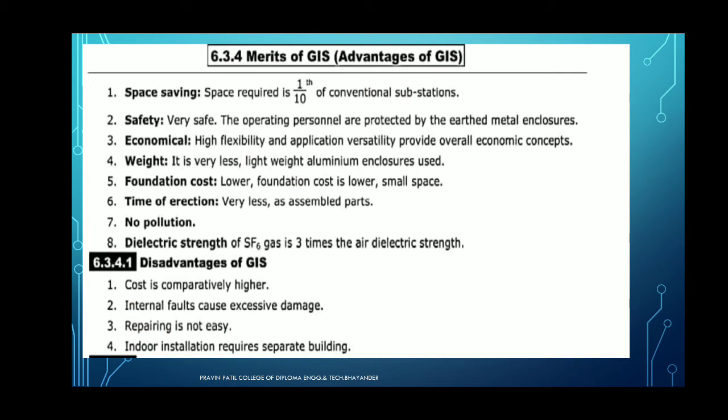Economically it has high flexibility, is applicable and versatile, and provides an overall economic concept. Its weight is very less, light in weight because of the aluminum enclosure. Foundation cost is lower as small space is required. Time of erection is very less, as parts are assembled. No pollution. The dielectric strength of SF6 gas is 3 times the dielectric strength of air.